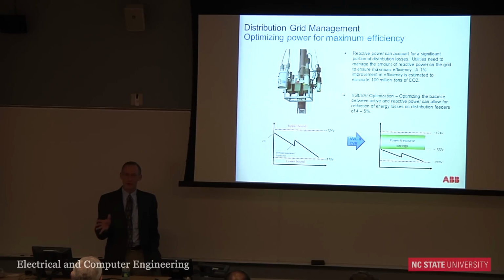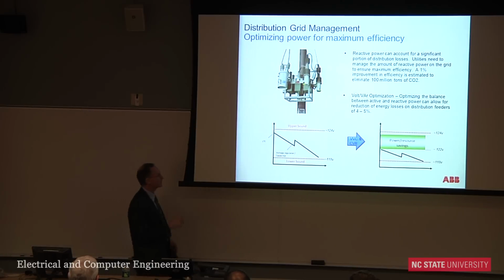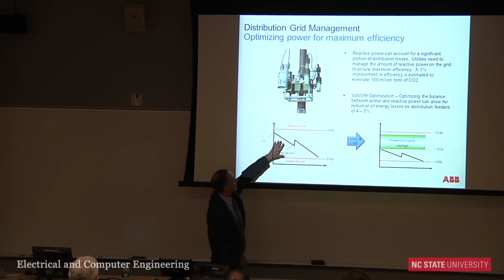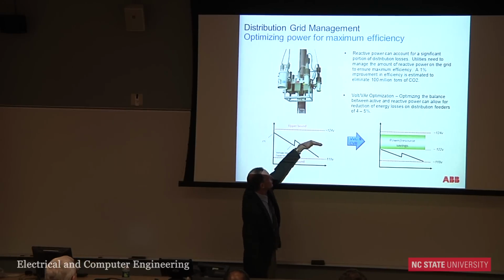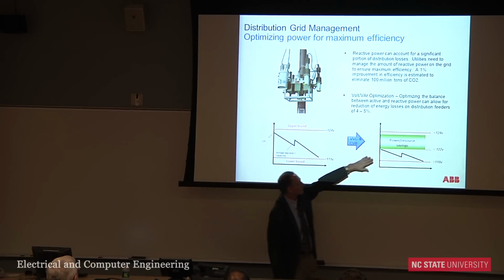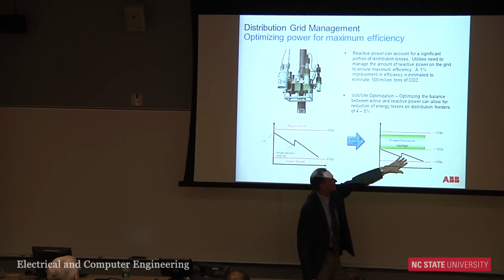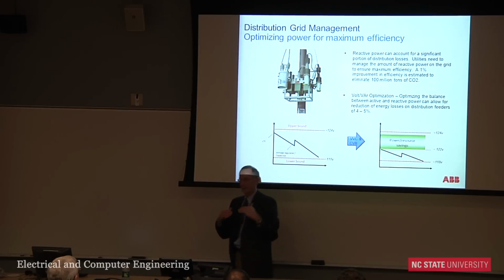Reactive power isn't real power, but when it pushes back to the generation, it's real fuel going into those generators, and real capacity in those generators feeding those reactive losses on the distribution grid. So there's a lot of money that can be saved by eliminating those losses. Now, if you lower or reduce the amount of regulation, giving a more horizontal curve as shown here, you can lower the voltage.